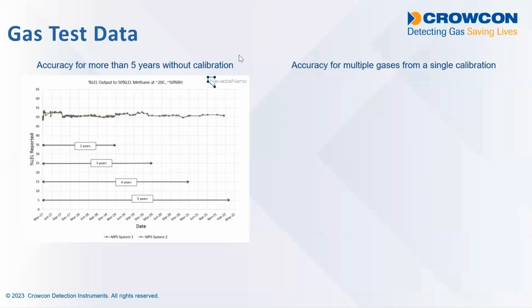Okay, so we have some data that's been derived in our laboratory at Crowcon. Here on the left, you can see 5 years' worth of data to demonstrate that the MPS sensor doesn't need routine calibration. You've got data points across a 5-year period where gas has been applied without recalibration of the sensor, and the signal still remains accurate and consistent. So it really doesn't need calibration.